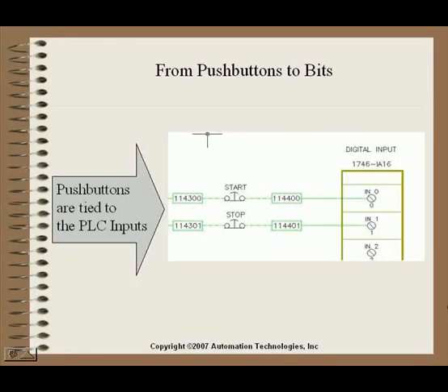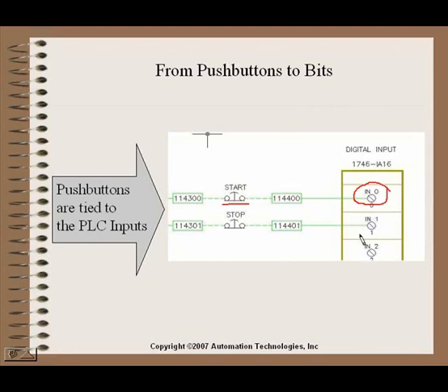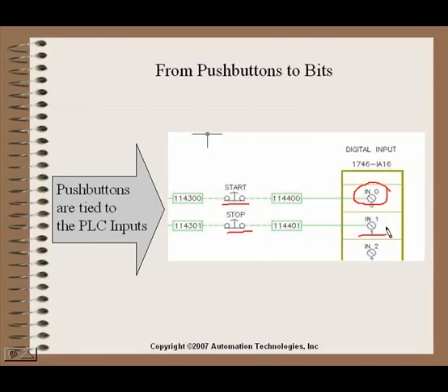So what's the difference between the PLC and the regular hardwired option? Well, with hardwired, you saw we take our push buttons directly to a relay, and it acts directly upon that relay. With the PLC, we have our start button, and it actually comes into an input card. It's wired directly into cards that interface directly to the processor through a rack or some other means. So both our start and stop push buttons from our previous example both come in to an input card, and then they can be used and processed. We'll see that later when we get into the PLC program. They can be manipulated inside the PLC program.